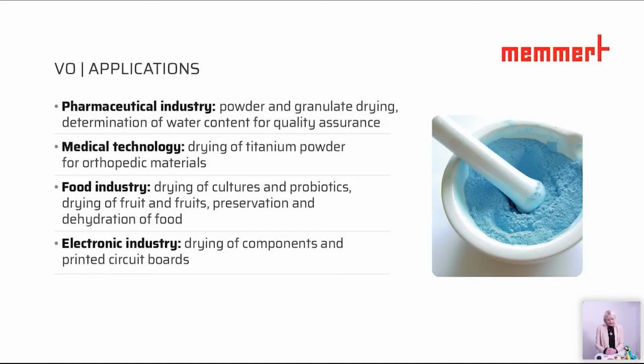Let's go further. So, medical technology. We have here drying of titanium powder for orthopedic materials. Let's talk here about implants, for example. What does it mean? We need a high grade purity of this titanium powder. And that means here we have to do some special processes. First of all, we have to add hydrogen, and then we can do our grinding process and this crushing. By this way, there will be some small parts and there will be some ferromagnetic parts. And this will have to be taken out because we need high purity of this titanium powder when we go into the medical field. For this reason, a vacuum oven is used, and here the drying will be done after the hydrogen has been added. So that means the vacuum oven is used for getting a very high purity titanium powder.